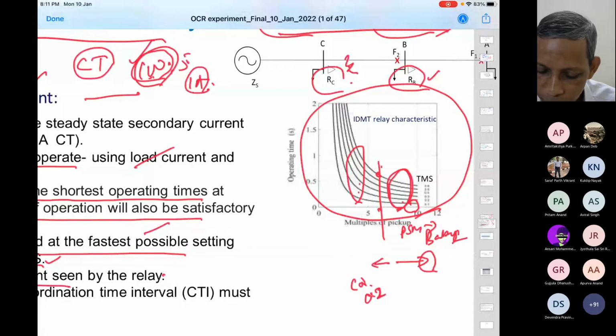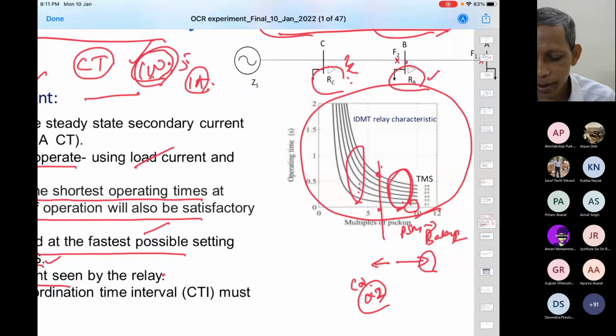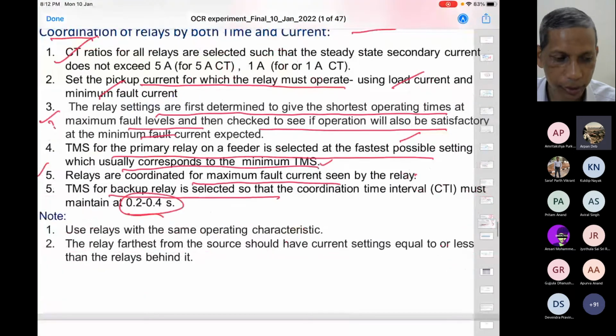If you maintain the coordination time of 0.2 at the minimum fault current level, then on the right-hand side it will be less. You follow? So when you are coordinating 10 or 15 cycles between this relay and this relay, you maintain it at the maximum fault current associated with that arrangement, on the right-hand side, not the left. Then you ensure that at the minimum fault current level the coordination time will also be maintained, and it will be more. From this curve, the gap between any two curves on the right-hand side is small compared to the time gap on the left-hand side.